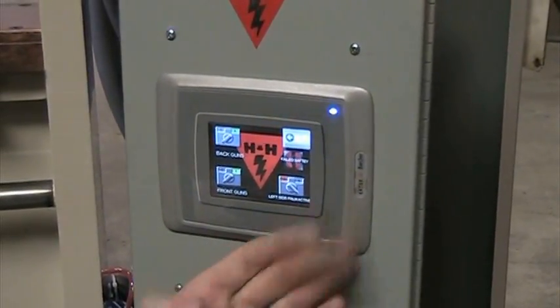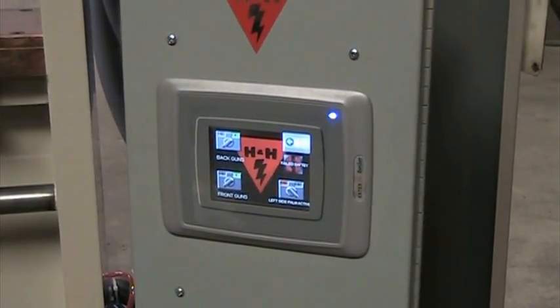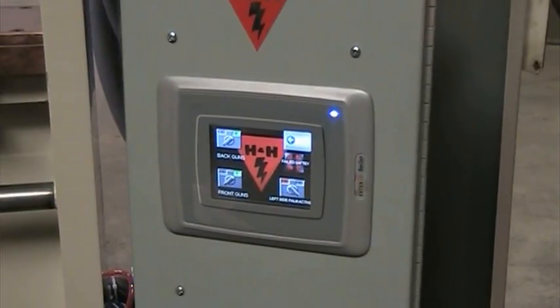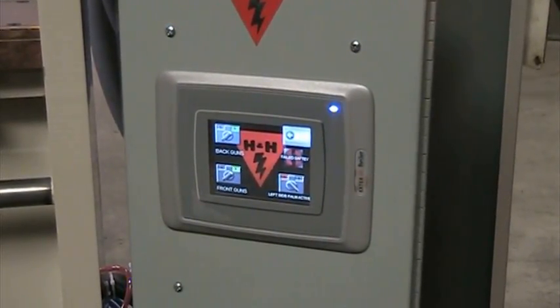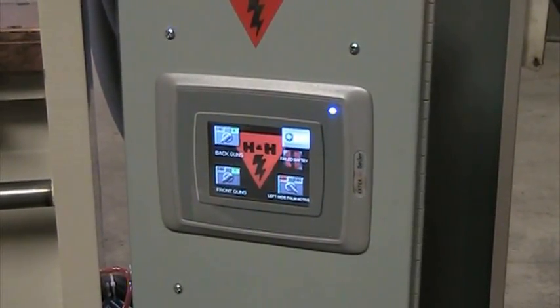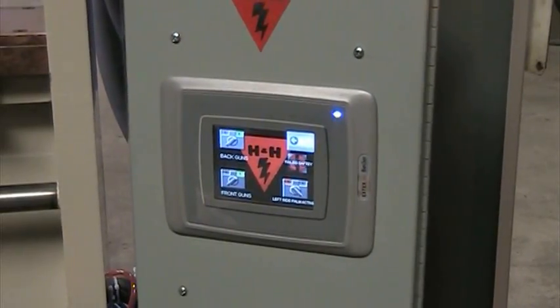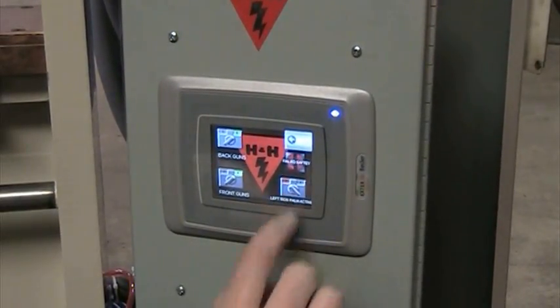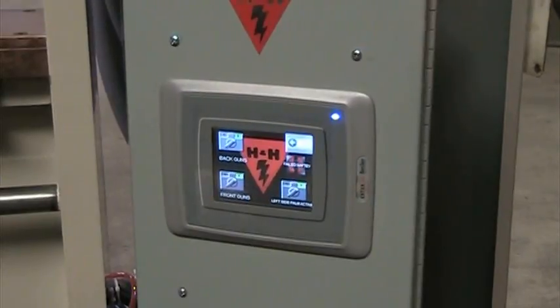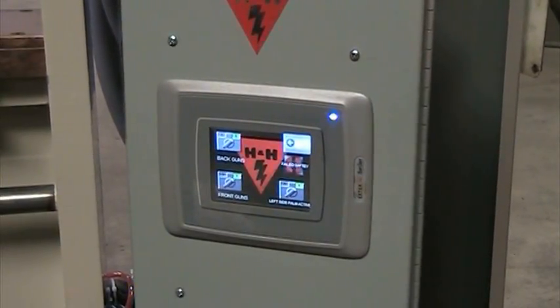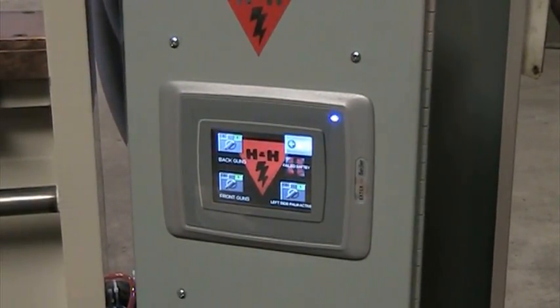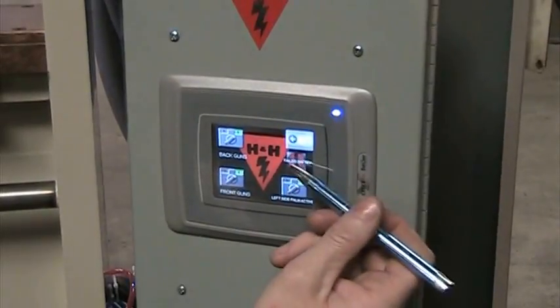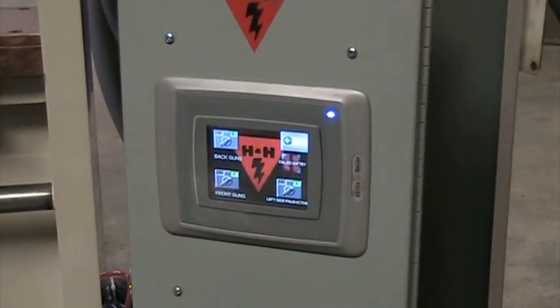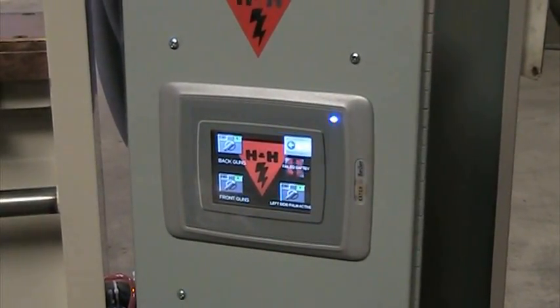Also, here on the right hand side, you've got the left palm active. The default state is for it to work with only the control side palm button stand active. But if you have 2 operators on the machine, then you need to energize the left hand side palm button, and now both palm buttons have to be depressed for the machine to actually do a sequence. And then you have the failed safety illuminated to show us that we don't have water flow at this point.